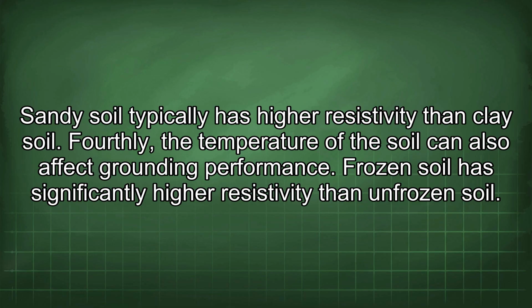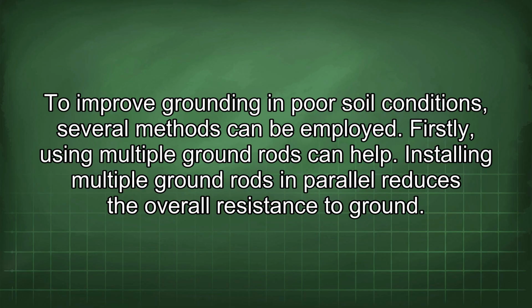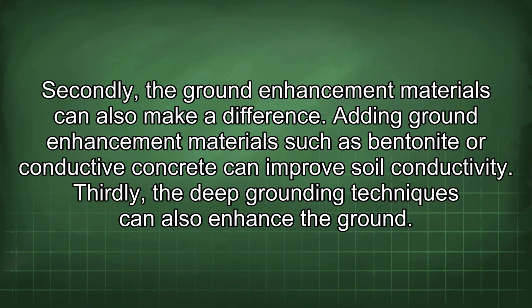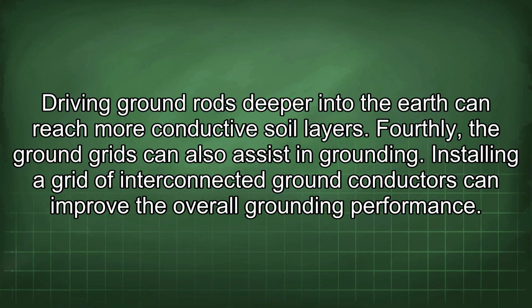Fourthly, the temperature of the soil can also affect grounding performance. Frozen soil has significantly higher resistivity than unfrozen soil. To improve grounding in poor soil conditions, several methods can be employed. Firstly, using multiple ground rods can help. Installing multiple ground rods in parallel reduces the overall resistance to ground. Secondly, the ground enhancement materials can also make a difference. Adding ground enhancement materials such as bentonite or conductive concrete can improve soil conductivity. Thirdly, the deep grounding techniques can also enhance the ground. Driving ground rods deeper into the earth can reach more conductive soil layers. Fourthly, the ground grids can also assist in grounding.